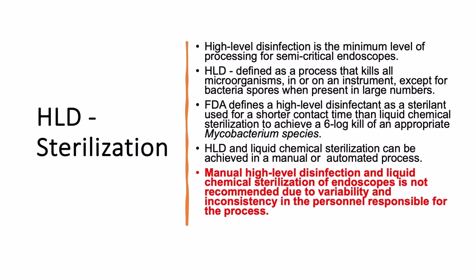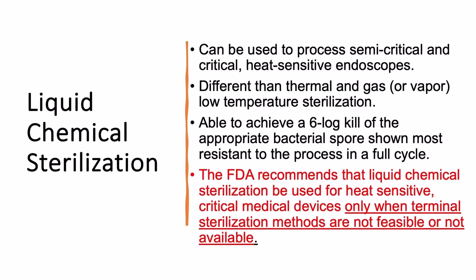Liquid chemical sterilization can be used to process semi-critical and critical heat-sensitive endoscopes. It's different than thermal and gas vapor, low-temperature sterilization, and it can achieve a 6-log kill of the appropriate bacterial spore shown most resistant to the process in a full cycle. But the FDA recommends that liquid chemical sterilization be used for heat-sensitive critical medical devices only when terminal sterilization methods are not feasible or not available. So again, they're pushing us over to sterilization.